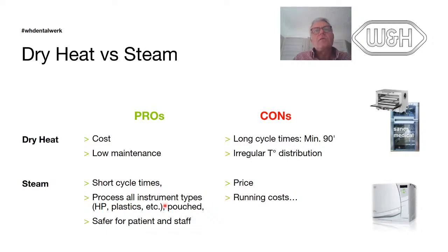The cons, yes, it costs money, but it's quite nice because you use a machine that safeguards and checks her performance or his performance. And you work at high standards. Obviously, running costs, you have to change the door gaskets, what you actually should also do with your dry heat, but you never do it, do you? So you change the door gasket, but it's like 20 euro every 800 cycles, so it's not much. And these machines, our machine does not require any service before 4,000 cycles. This is many years of use before you can service.